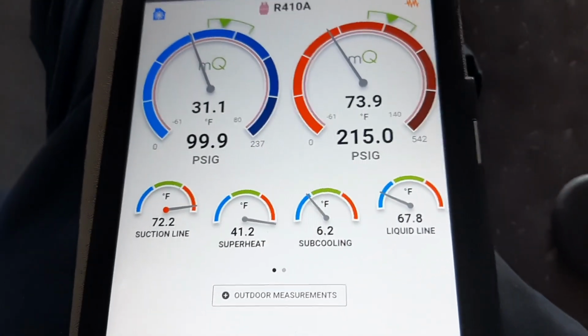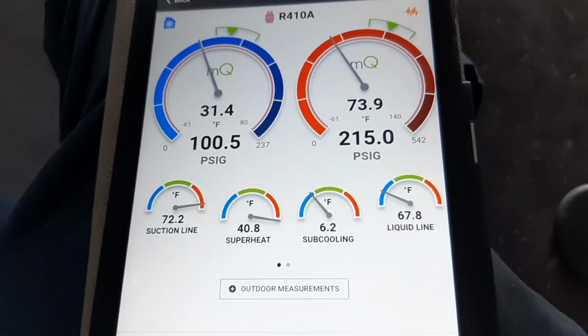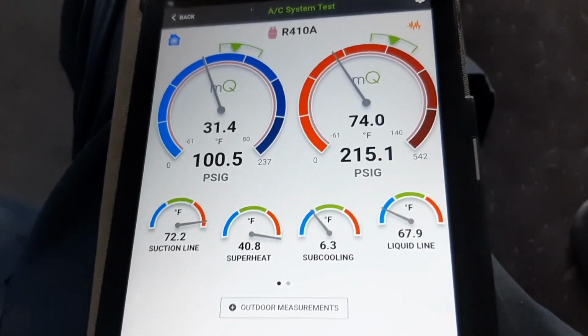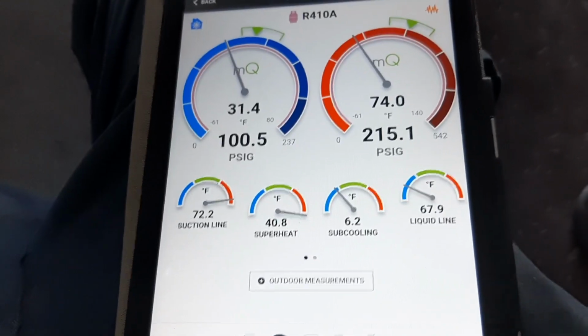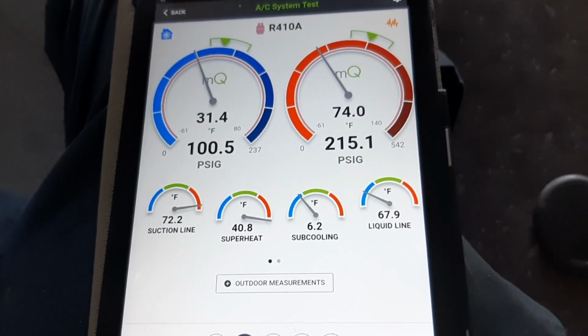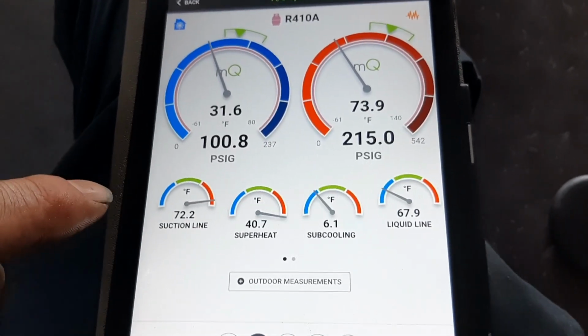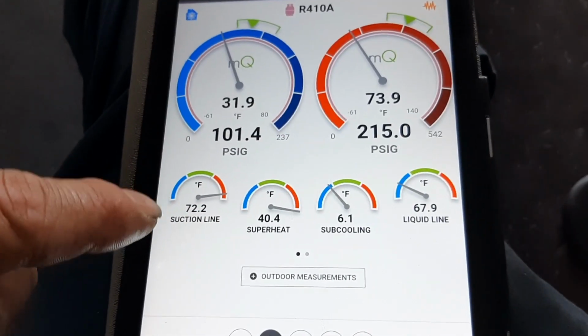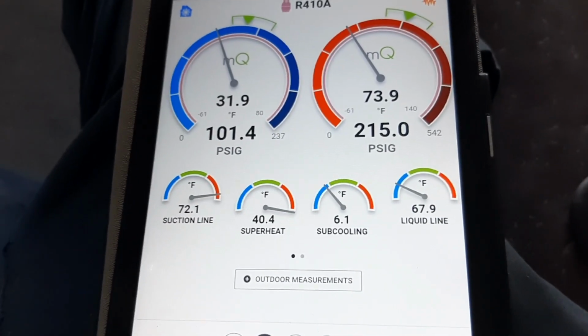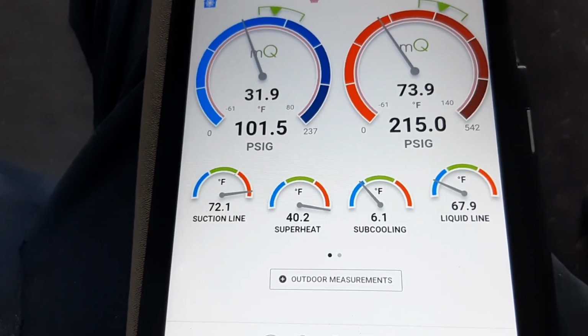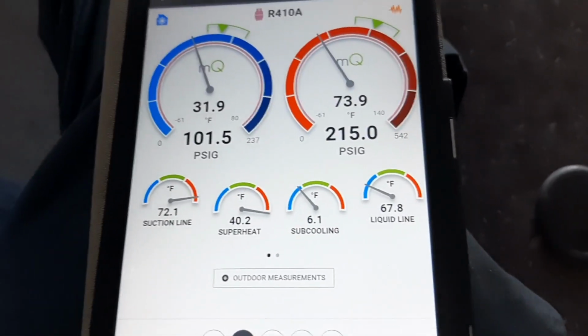The superheat's concerning. Subcooling looks reasonable right now, but after some run time, it might improve. I'm gonna have to go outside and make sure I'm reading that suction line temperature, because it ain't really moved. But we're gonna let it run for a little while and check on some things.